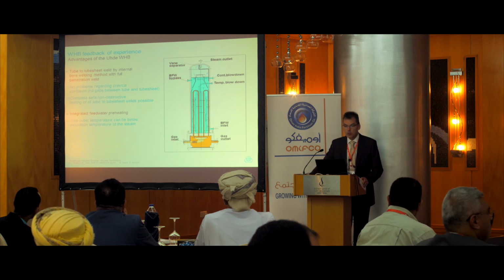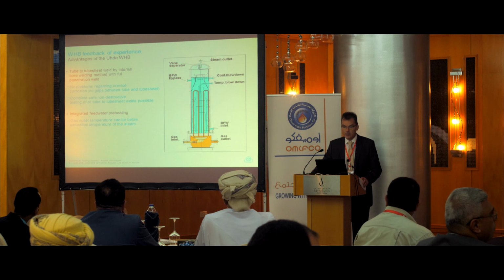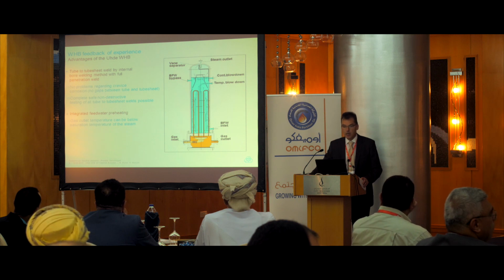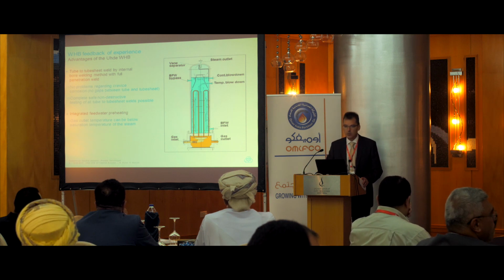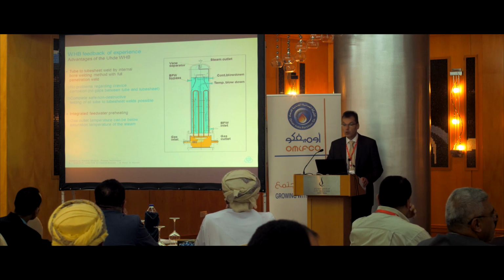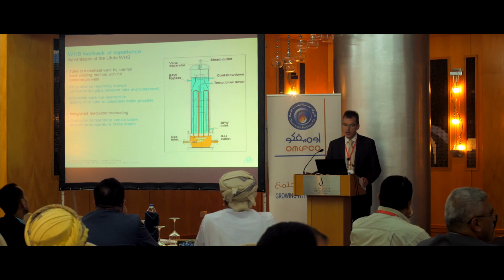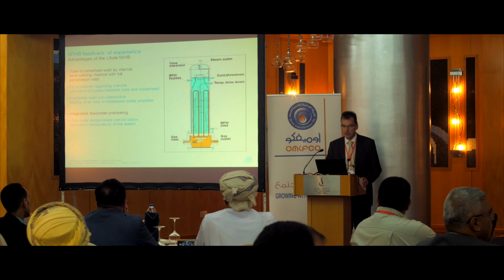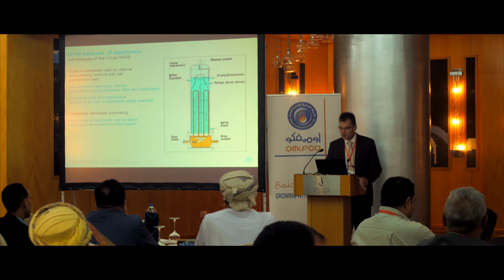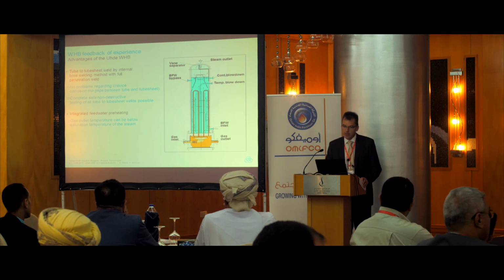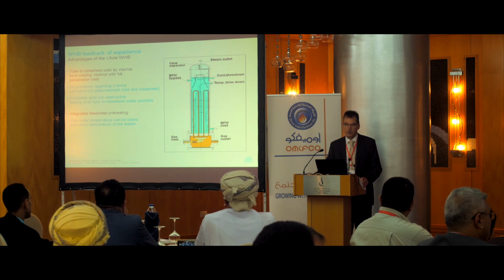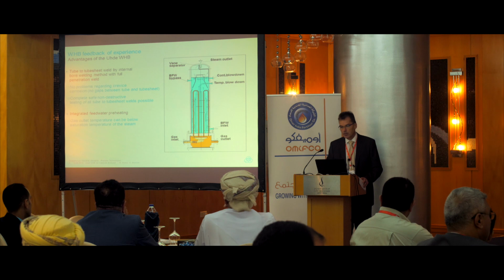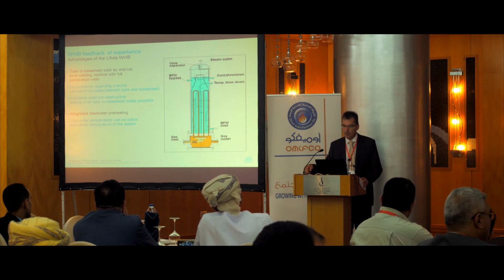Other features are tube-to-tube sheet weld by internal bore welding method with full penetration weld. I will show you one slide, just a picture, so that you see what this so-called internal bore welding is. That means no problem regarding crevice corrosion, because there are no gaps between tube and tube sheets. In other designs, the tubes will go through the tube sheet, and even if you roll them on the tube sheet, you will have small gaps, which will risk later on that impurities will collect there and you get corrosion at this area.